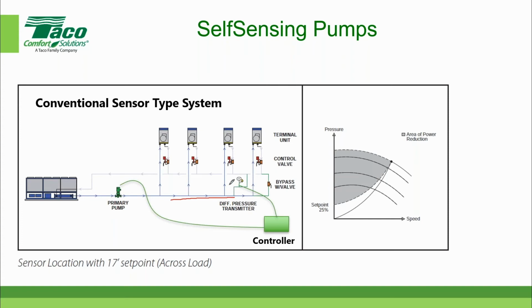So we're measuring the pressure differential. And what are we actually measuring for the pressure differential? We're measuring the pressure drop at the maximum flow for the terminal unit for the following 5 major components. And that includes the fan coil itself, which is usually the coil inside the fan coil. It includes the strainer, the balancing valve, the control valve, and the isolation valve.